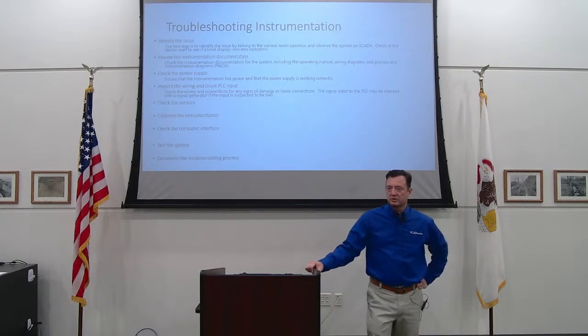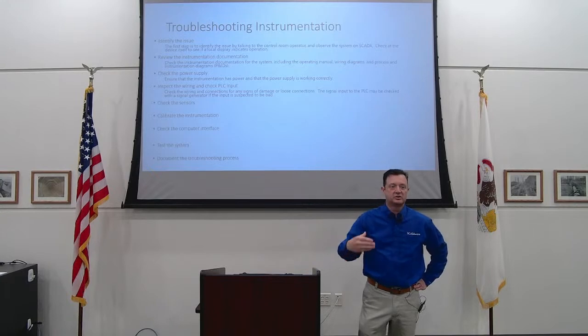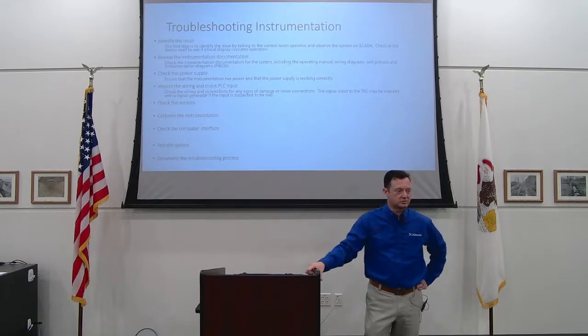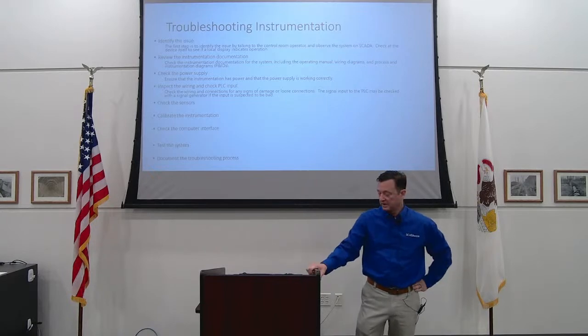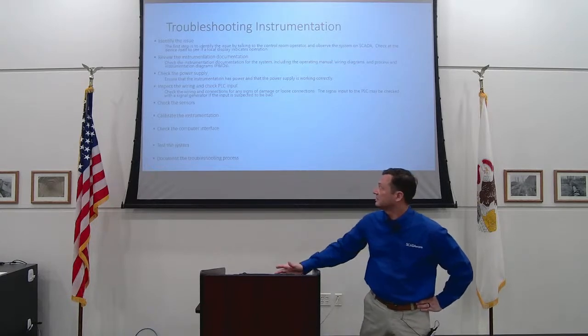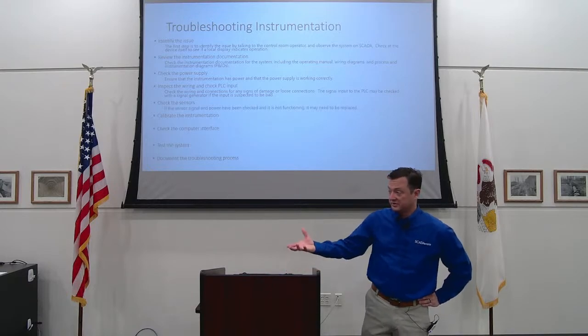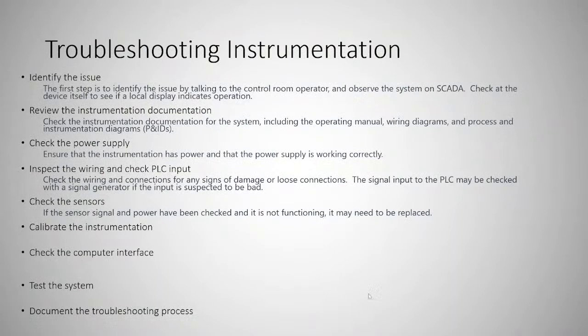If you have an integrator on site, it's good to have them teach some of those troubleshooting components, to be able to say, this is how you'd check the signal on a level transmitter, and you can take this wire off and stick your meter here, to give you guys some more tools to support that. Go out to the sensor itself, obviously. Especially if it has a display, is it reading at the sensor and not reading at SCADA or at the PLC? But if it's dead out there and you've got power to it, then you've got a bad sensor. Check calibration on it. Maybe it's reading out there and is just reading wrong into the SCADA system.